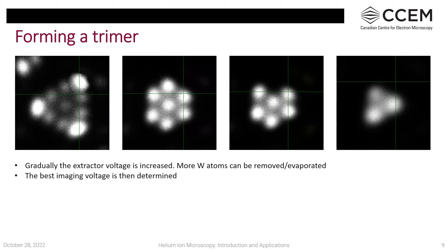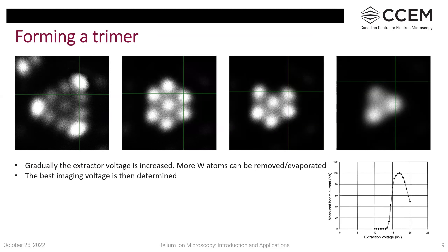The next step is finding the best imaging voltage by sweeping the extractor voltage to find the highest emission current. You can monitor either the trimer intensity or the measured beam current to find the maximum value. This process needs to be done on average every one week to one month. If using neon gas, you may need to reform the trimer more frequently.